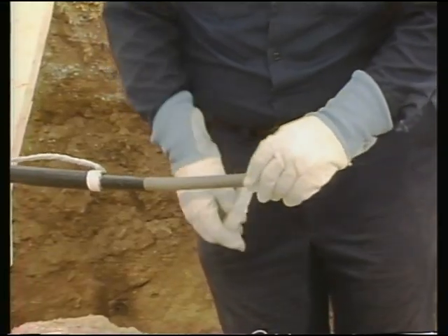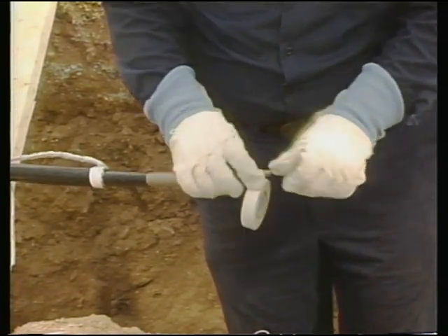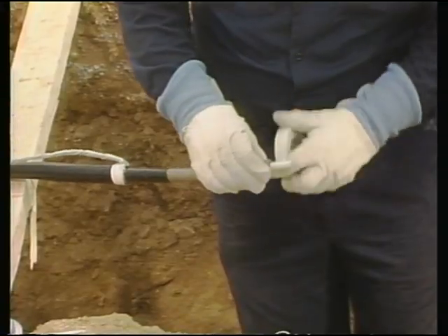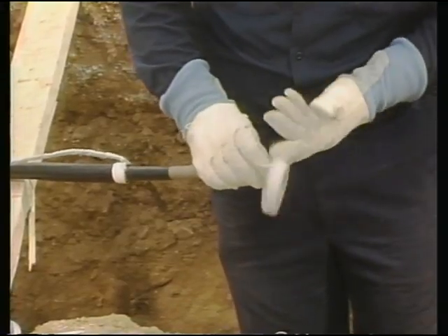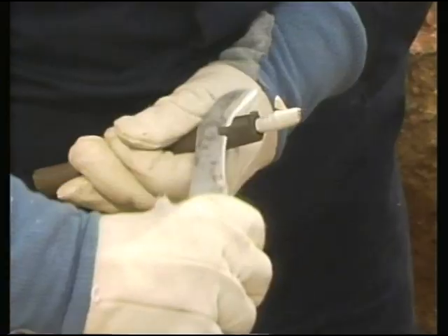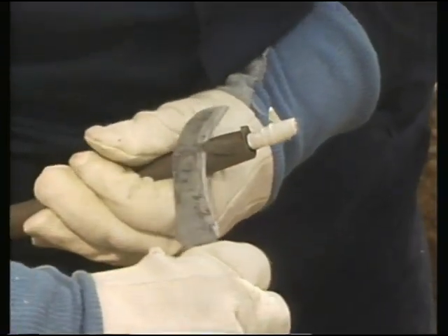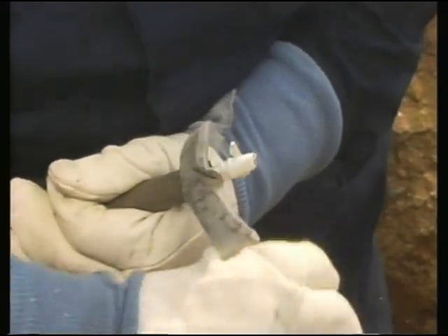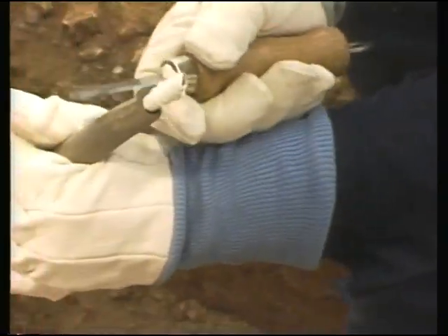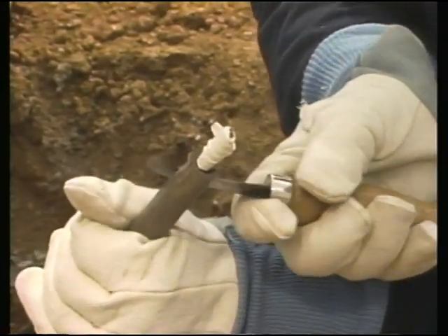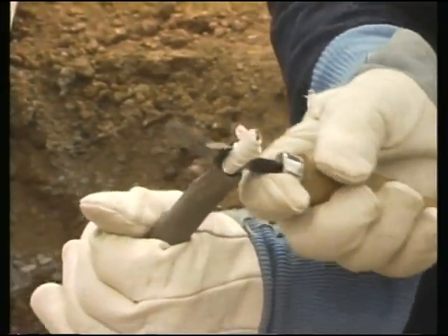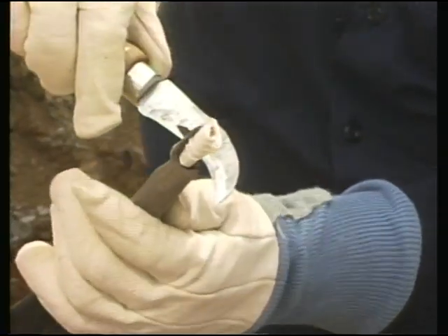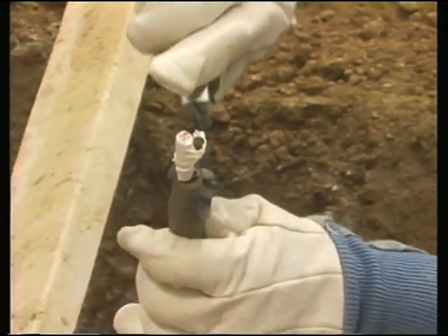The tapering can be done in a couple of ways. If a knife is going to be used, a protective layer of tape should first be placed over the conductor to protect it from being nicked accidentally. By using the knife, the workman cuts the cable to the desired slope. The knife is just one of several tools that can be used to pencil. Whatever method is used, though, it's important that the cable conductor not be nicked or otherwise damaged during the process. Now, after the penciling, what remains is a cable that is ready to be spliced.